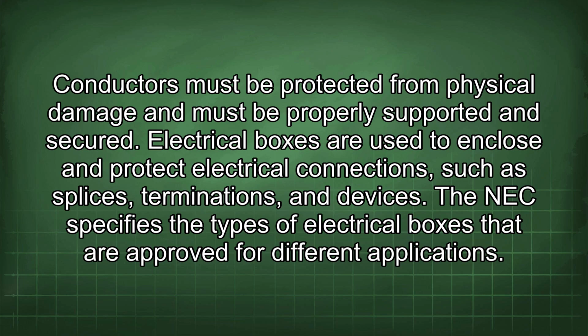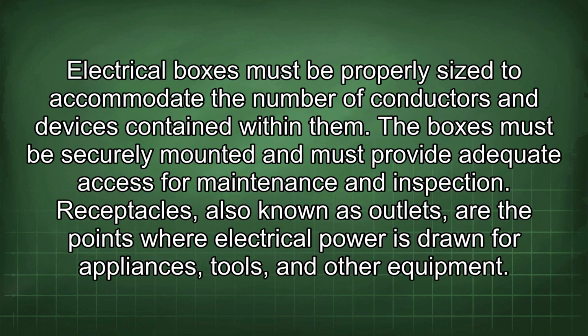Electrical boxes are used to enclose and protect electrical connections, such as splices, terminations, and devices. The NEC specifies the types of electrical boxes that are approved for different applications. Electrical boxes must be properly sized to accommodate the number of conductors and devices contained within them. The boxes must be securely mounted and must provide adequate access for maintenance and inspection.